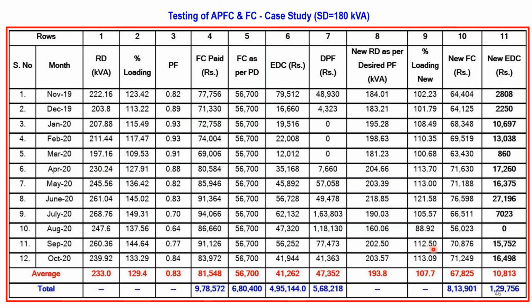Now this is a complete electrical energy consumption pattern of an industry, from a recently conducted study, where the sanctioned demand of the company is 180 kilowatt, 180 kVA. It's an HT industry. Now you can see the recorded demand. Recorded demand is going to be almost higher, and the percentage of recorded demand by the sanctioned value is going to be almost more than 100%. Because of the more than 100%, it invites penalty, EDC penalty.